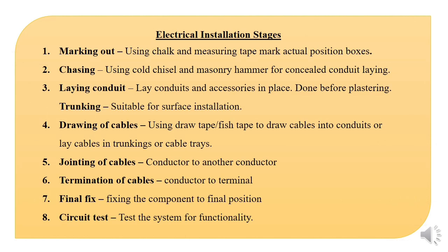So what are the stages you have to go through while carrying out installation? Stage one is marking out. Marking out is using chalk or anything that can leave a mark on the wall, ceiling, or floor wherever we are going to place our components. You need to know the measurements, which are guided by standards. They vary depending on the nature and purpose of the building and the weather conditions. For example, socket outlets in a damp area may be placed higher than the standard 19 inches from the floor.